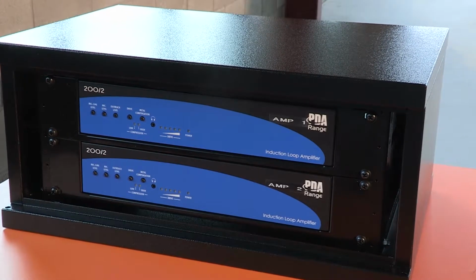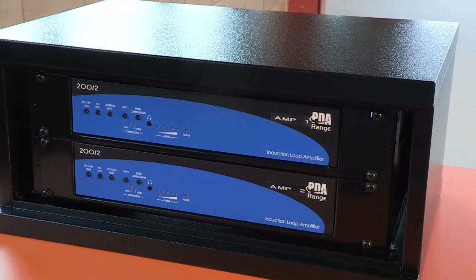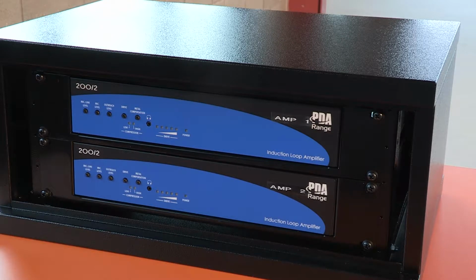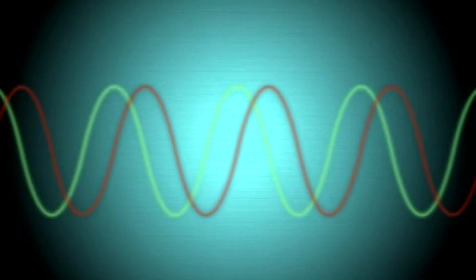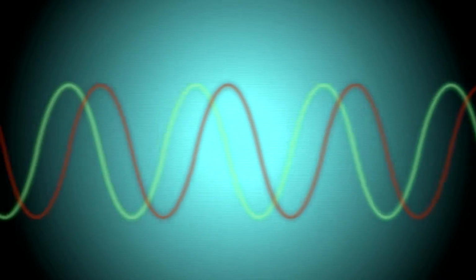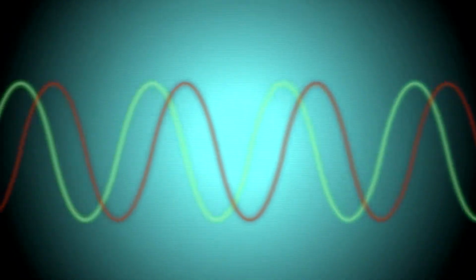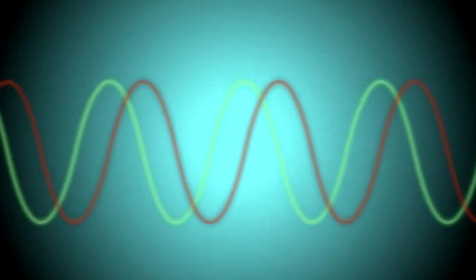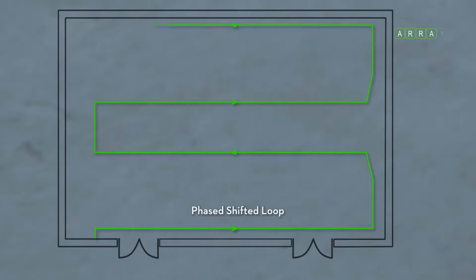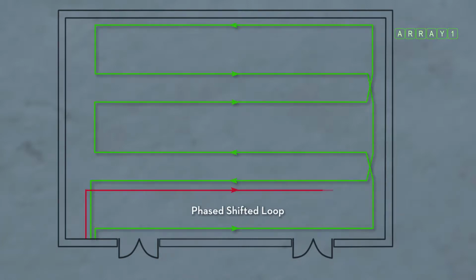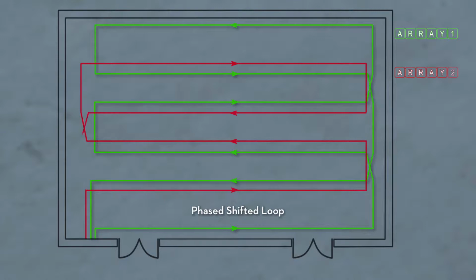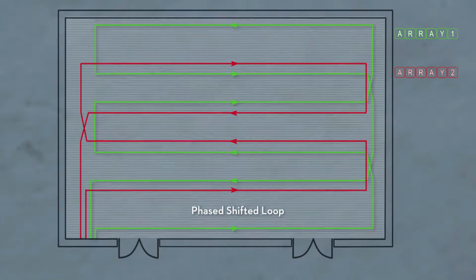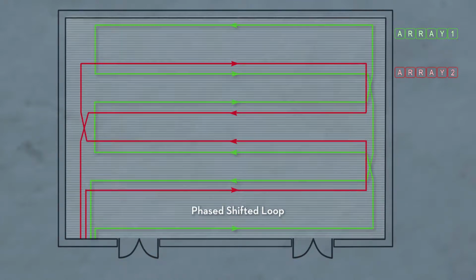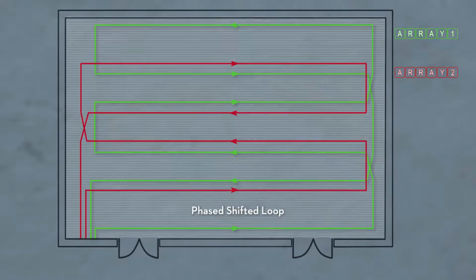This is how a phased array hearing loop system works. A phase-shifting amplifier produces two signals that are 90 degrees out of phase with each other. These signals are connected to two hearing loops laid out in a special overlapping pattern. The resultant magnetic field is evenly spread within the covered area, and the field strength falls off very quickly outside the loop.